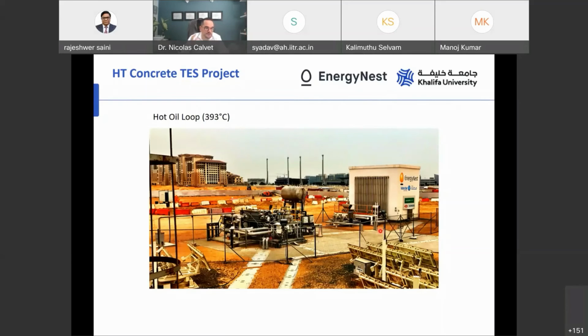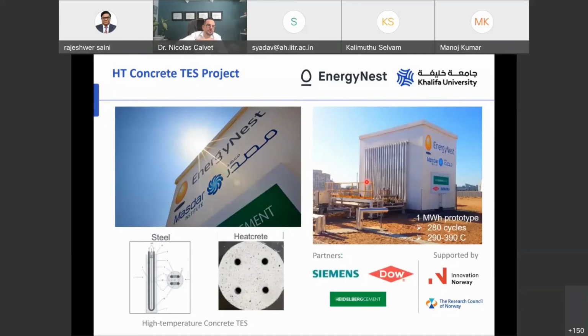So keep in mind that here we want to test the storage unit, which is here. And so the goal is to charge and discharge as fast as possible. So we did almost 1 year of experiment, charging during day, discharging during night. So here the storage pilot, basically we have concrete columns, so 5-meter high columns. They are vertical in this pilot, but in the commercial, now they are horizontal. Doesn't change much. You have a U-shape, double U-shape heat exchanger embedded inside the concrete column.